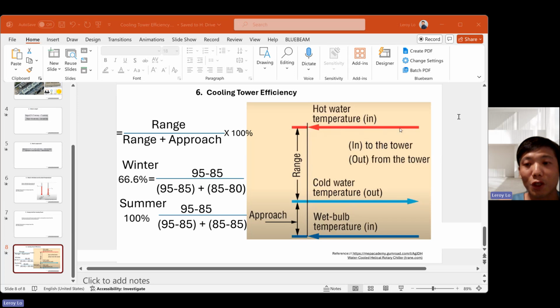For 100% cooling tower efficiency, in practice the cooling tower efficiency will need to be between 70 and 75. Normally, you need to account for the summertime. In summertime, you want to keep it at 70 to 80, maybe 85-ish. The ambient air wet bulb temperature rises in the summertime compared with the wintertime, so cooling efficiency limiting in the summertime is very common.